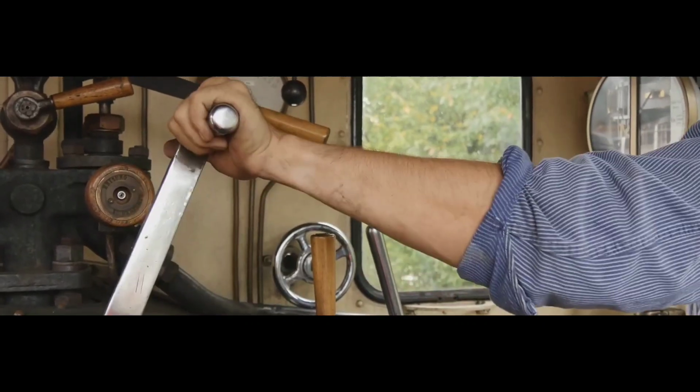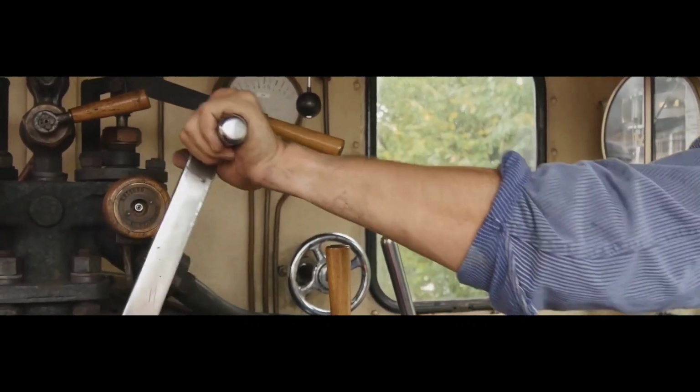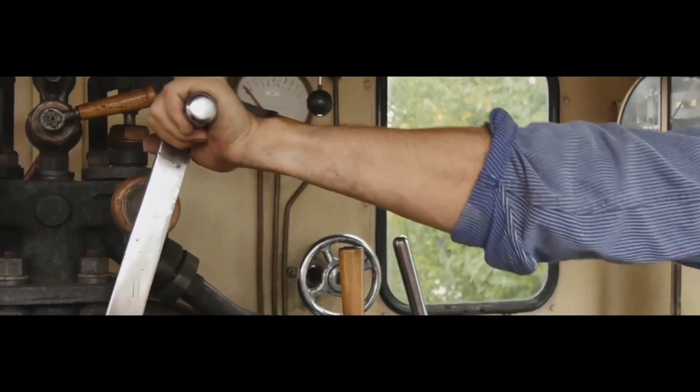Series motors, on the other hand, have their field winding in series with the armature. This setup delivers massive starting torque, making them ideal for heavy-duty jobs like powering trains, cranes, and hoists, anywhere you need a big push to get things moving. However, there's a catch. If the load on a series motor suddenly drops or is removed, the motor can accelerate uncontrollably and reach dangerously high speeds. That's why series motors must always be operated with a load attached.